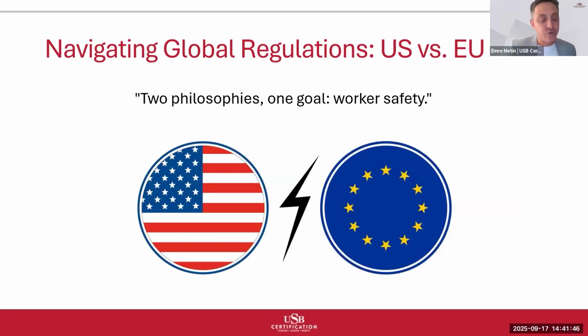Now let's step back and look at how different regions of the world approach arc flash protection. Understanding these differences is crucial for anyone working with international operations, equipment, or standards. We essentially have two primary regulatory philosophies worldwide, but both share the same fundamental goal, protecting workers from electrical hazards. In North America, we follow NFPA 70E, the standard for electrical safety in the workplace. This represents a quantitative engineering-based approach. NFPA requires specific arc flash hazard analysis and directly links calculated incident energy levels to PPE requirements through a calorie per square centimeter rating system.